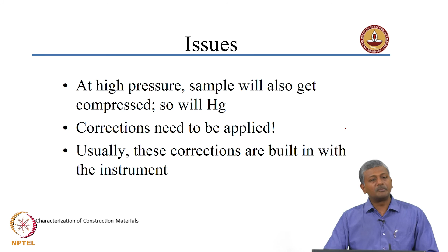At high pressure, you are compressing your sample and also compressing the mercury. So, there has to be some corrections applied for the compression. For most common samples, the instrument itself actually helps you apply those corrections directly. You do not need to physically do anything; the instrument has built-in corrections for the type of sample, and obviously for mercury there will be a standard correction for compression.